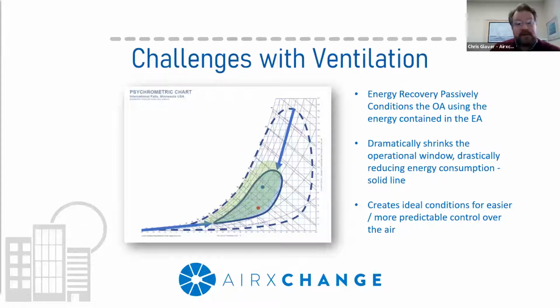And what it really does for you is it dramatically shrinks the operational window associated with ventilation air. So once again, looking at that psych chart, that dotted line represents the outside conditions without energy recovery, and that solid line represents the new operational window based upon including an energy recovery device. And really the difference between those two is the operational savings that these devices will get you.